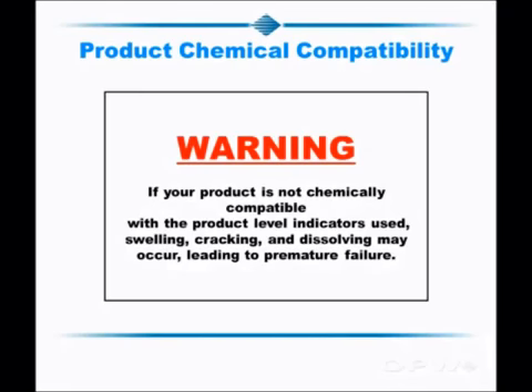Chemical compatibility. If your product is not chemically compatible with the product level indicators used, swelling, cracking, and dissolving may occur, leading to premature failure. Not only will the floats be damaged, there have been reported cases where the magnet itself in the float has been dissolved by the chemical in the tank.